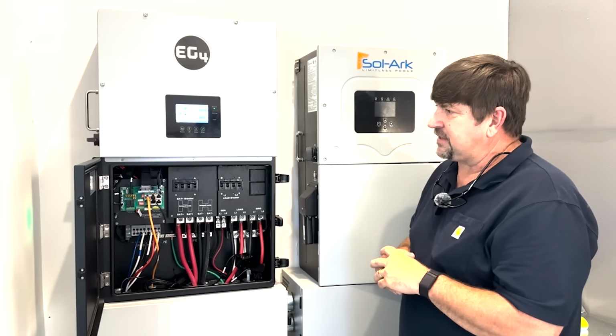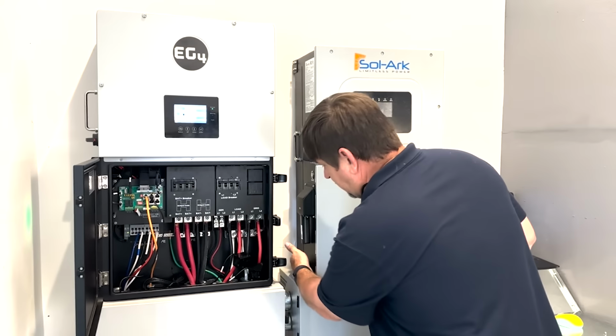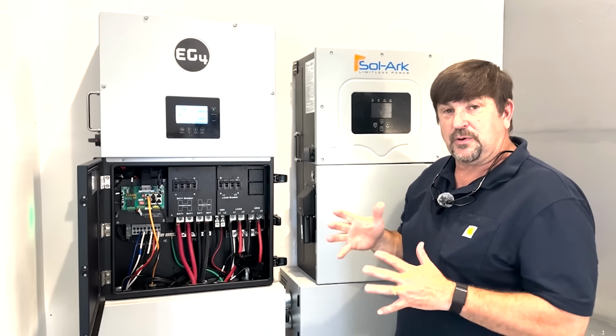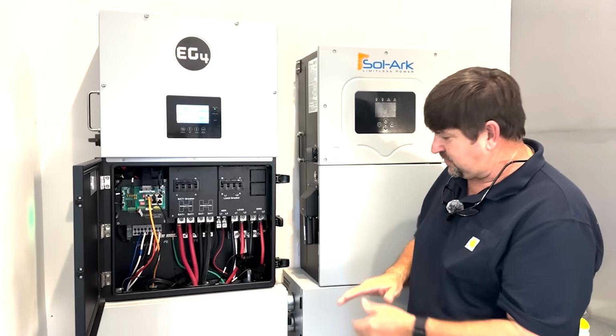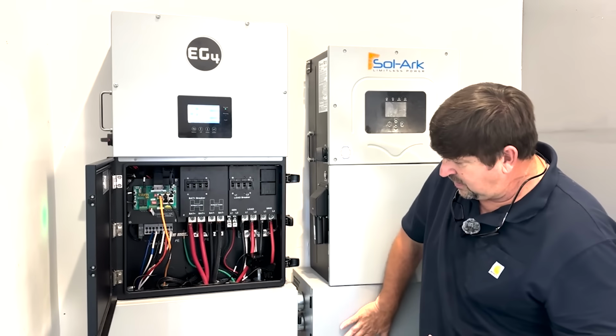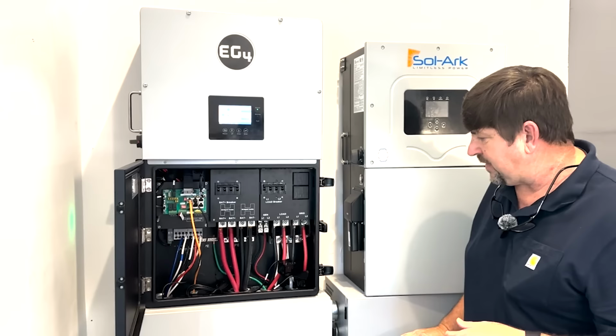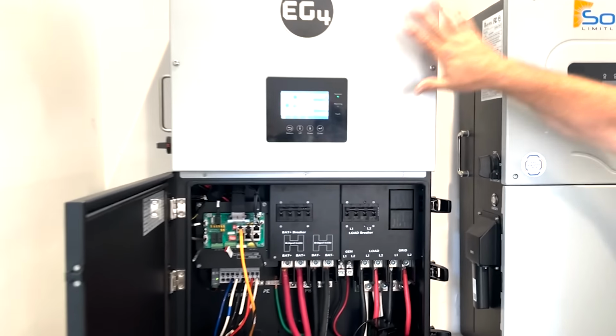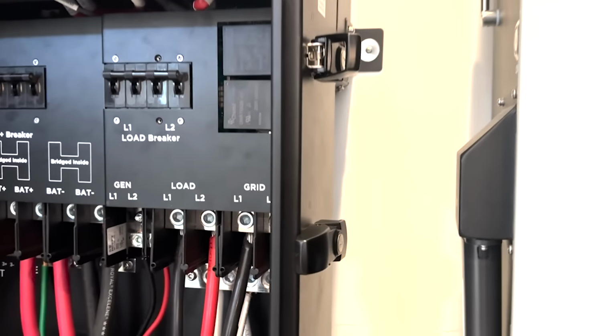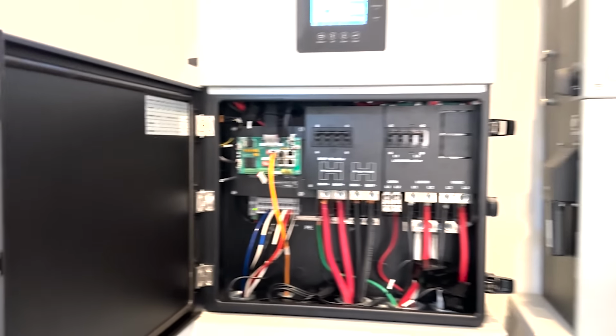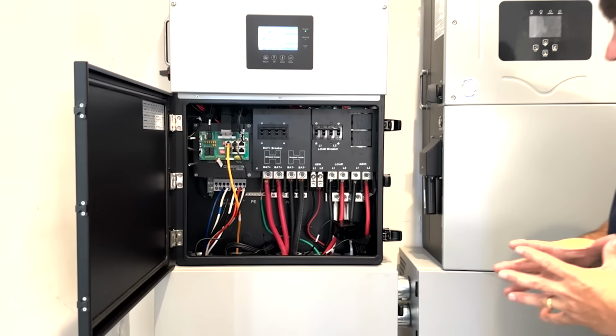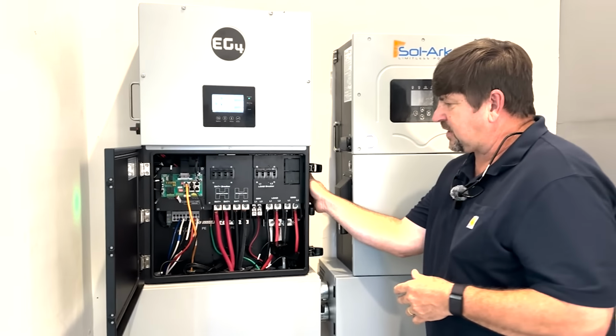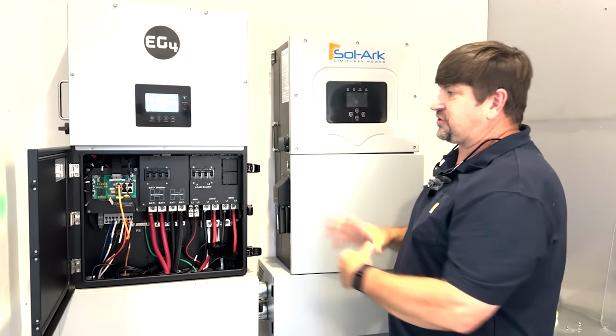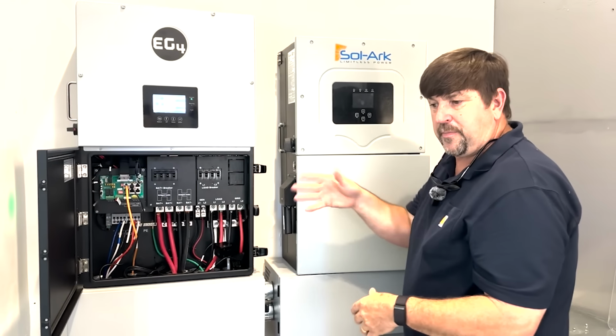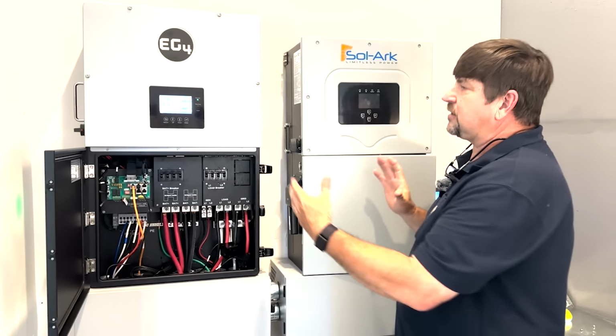One of the things they solved that Sol-Ark had a problem with is vertical venting. On the 12K it's not an issue, but on the 15K it is, because you can't mount it directly to a gutter unless the gutter has air channels, which Discover made a nice gutter for. This one is all open, which is why this inverter is taller—there's a lot missing behind here to allow for fans and airflow. That's the difference even though they're the same weight and size, same components, I think. The cutout lets air vent vertically, giving more room when installing, especially if you're paralleling units, so you can be closer together.